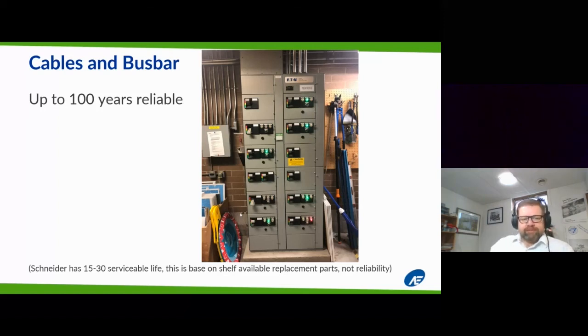Schneider says they've got a 15 to 30-year serviceable life. That means they've got shelf and store components available to maintain and replace whatever's there. So after 30 years, they might not be storing the components. I chuckle at this one because copper's copper. If I've got a 4-inch piece of 3/4 thick copper, it's copper, so I can always do some repairs there.